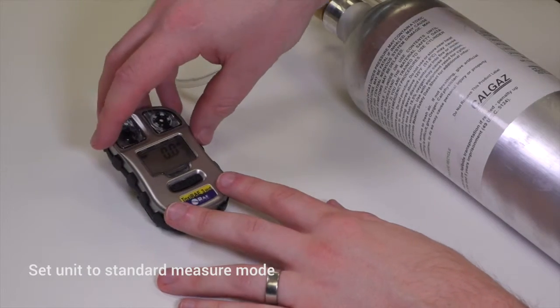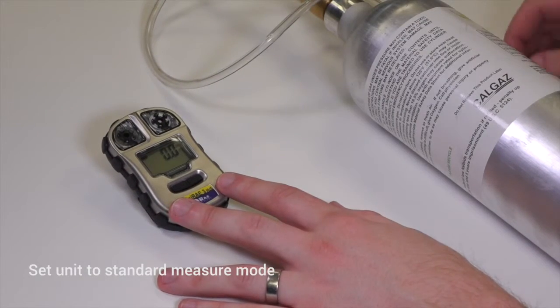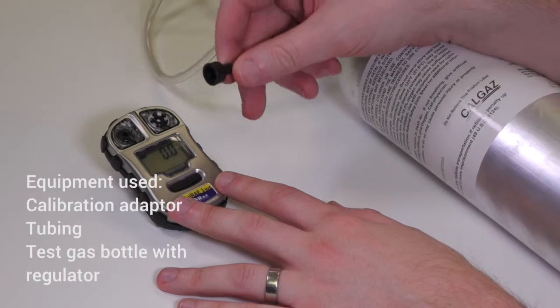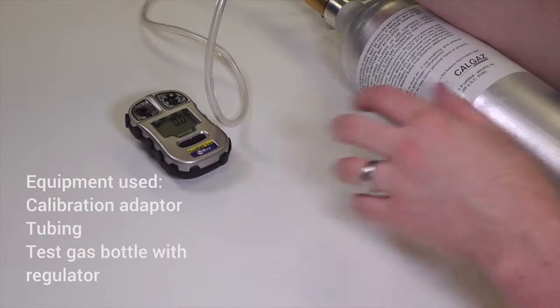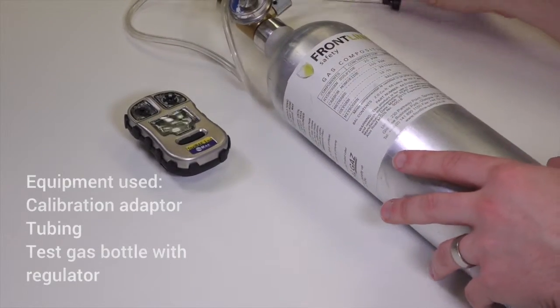Before you bump test the unit, it should be in standard measure mode. You'll need the calibration adapter which comes with the unit, calibration tubing, and a known concentration of calibration gas.